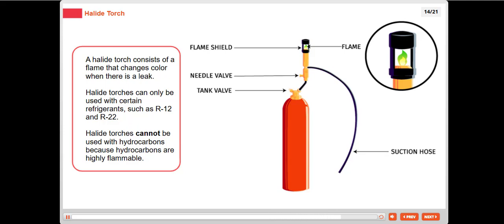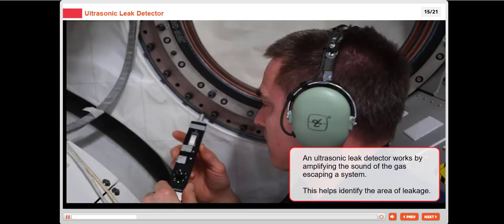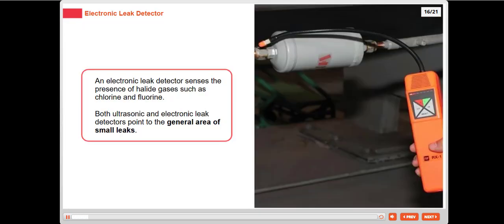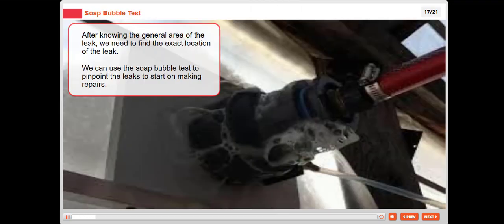An ultrasonic leak detector works by amplifying the sound of the gas escaping a system. This helps identify the area of leakage. An electronic leak detector senses the presence of halide gases such as chlorine and fluorine. Both ultrasonic and electronic leak detectors point to the general area of small leaks. After knowing the general area of the leak, we need to find the exact location of the leak. We can use the soap bubble test to pinpoint the leaks to start on making repairs.